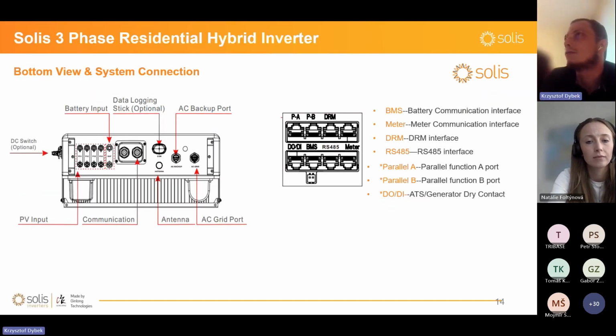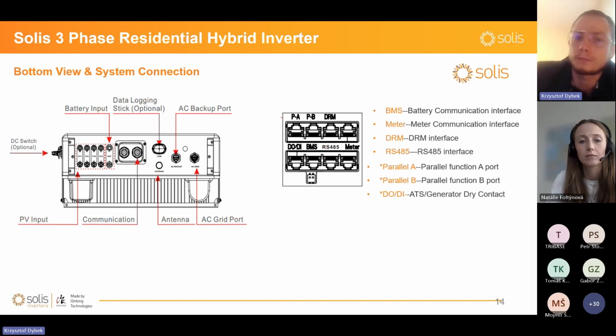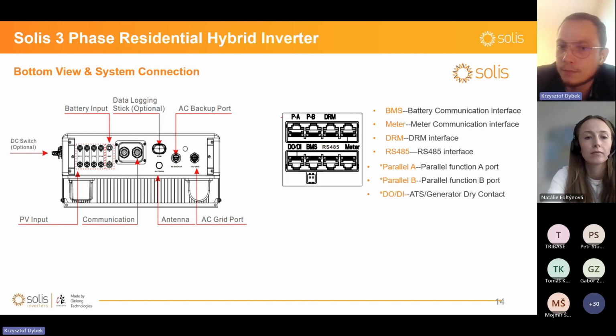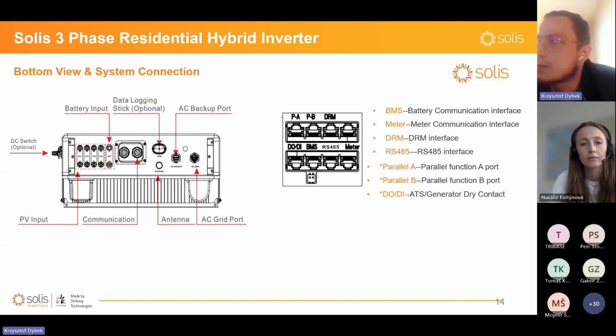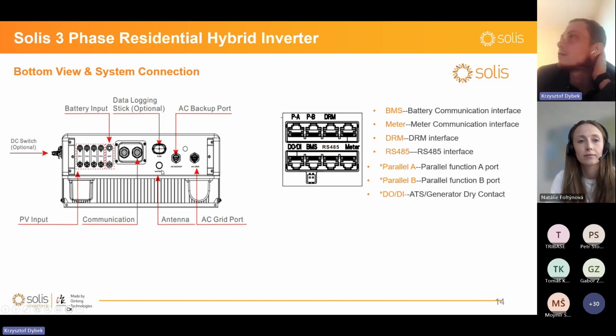What else can be said about this hybrid? This is how it looks from below. Ports are described basically on the slide. BMS is the battery communication interface. Here you would connect your CAN cables. Meter is an RJ45 or RS485 interface. Parallel A and parallel B are for paralleling inverters to have a cascading scenario. DI is the ATS generator dry contact port. The USB COM port is only for the new data logger type. You can't use it for any other USB device. I guess it is obvious, but I wanted to say it out loud. And here you have this AC grid. This is AC backup, and with commercial hybrids, you would have just one more with a diesel generator.